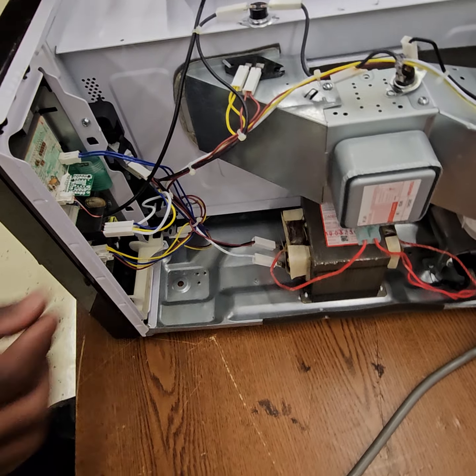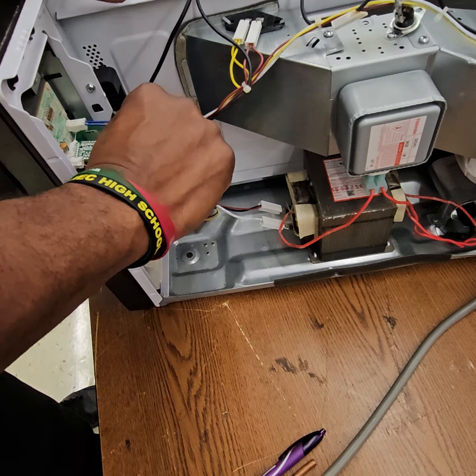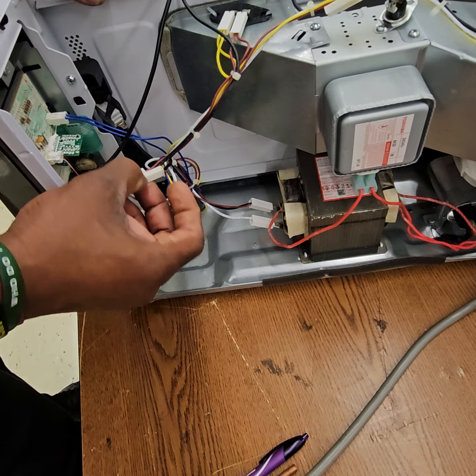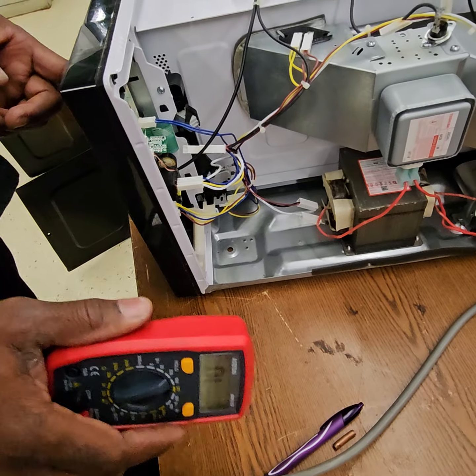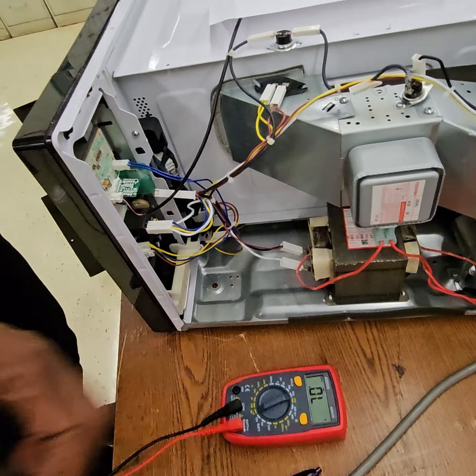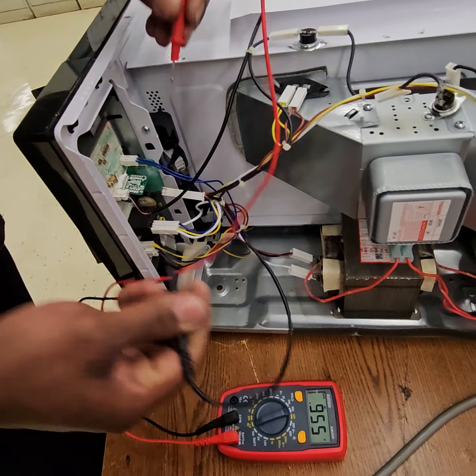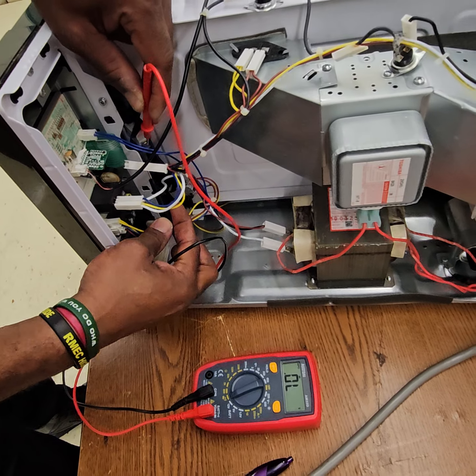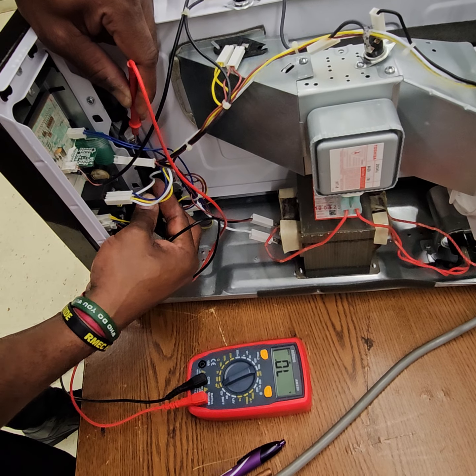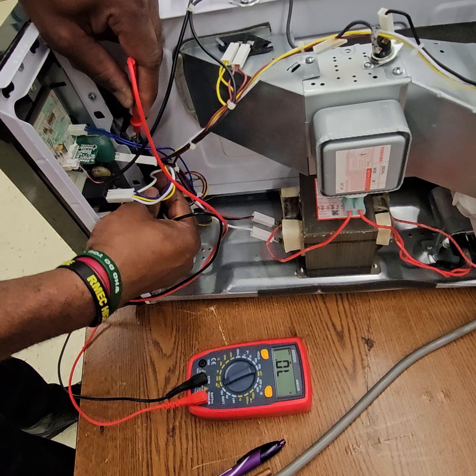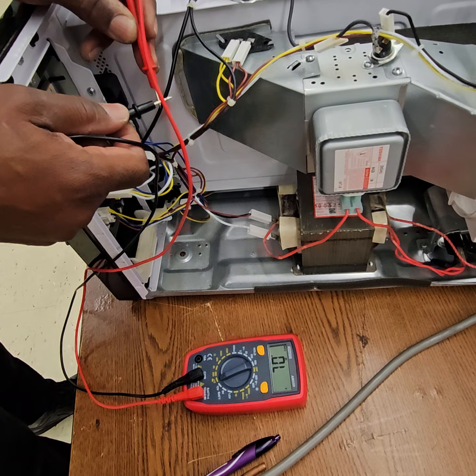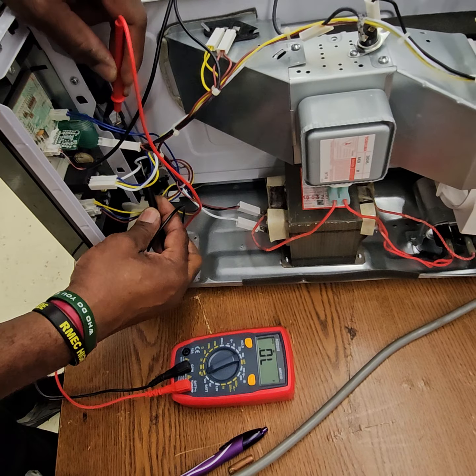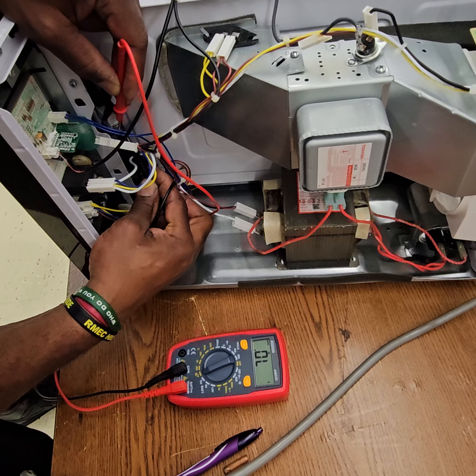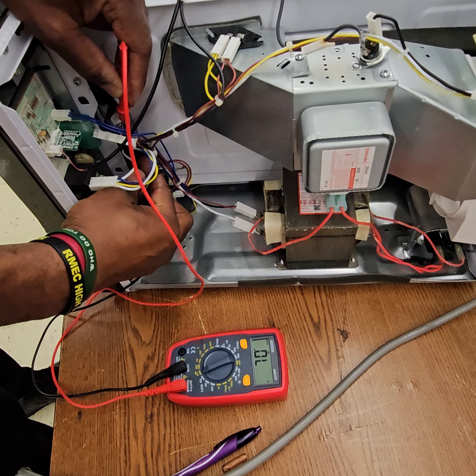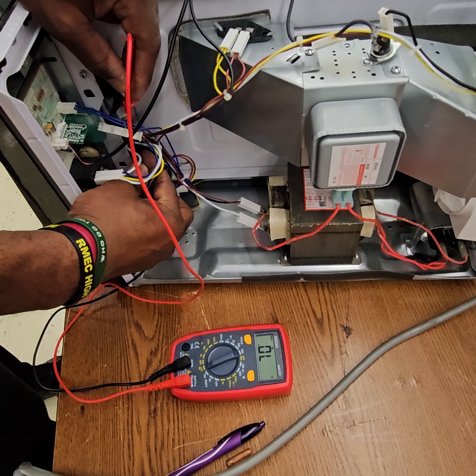Again, what I like to do is disconnect. I like to make sure I isolate my problem. I disconnect the switch. It's a quick disconnect so you can't mess it up, right? The door is closed in this position, so you should always get 0 ohms on a closed switch. So we go like this, and we check the switch, and we got infinite resistance. Let me zero my meter to make sure we're on ohms. Check it again. And we have an open line, which is a defective switch.